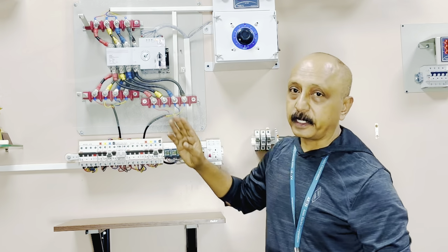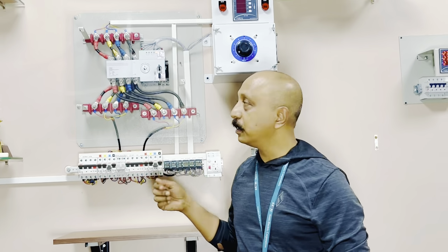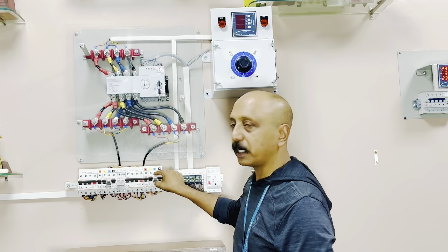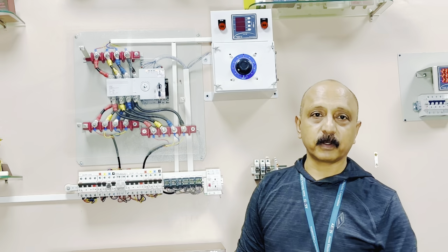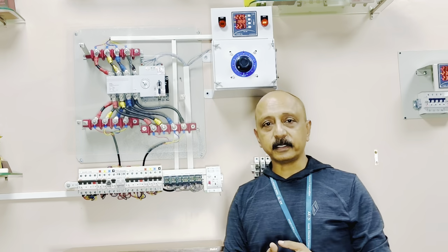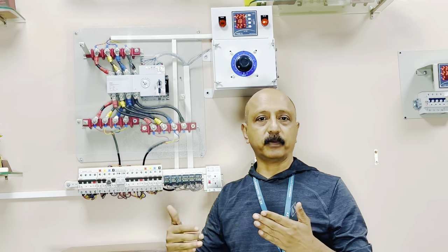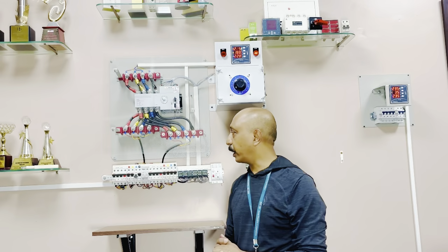So technically what should happen? It should move into the 0 position. So the ATS moves into 0 position. It cannot go into source 1 because source 1 already has a fault, and it can't move to source 2 because source 2 also has a fault. Now let's assume source 1, that is EB, comes back. So I'm switching on the Y phase of EB, and it goes into EB mode. What we are trying to tell you here is that the controller has the ability to handle subsequent faults, not only one fault. It can take 1, 2, 3 faults and similar, and it can function as it is logically programmed.